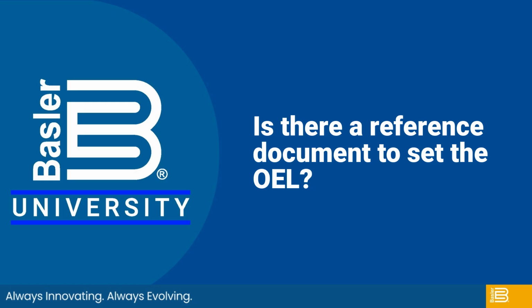The 105, 125, and 165 for the low level, medium level, and high level come from one of our field service engineers. We don't really have a white paper on it. IEEE may define some values, or if you're in a region where you have a governing entity for excitation, they might define some values.